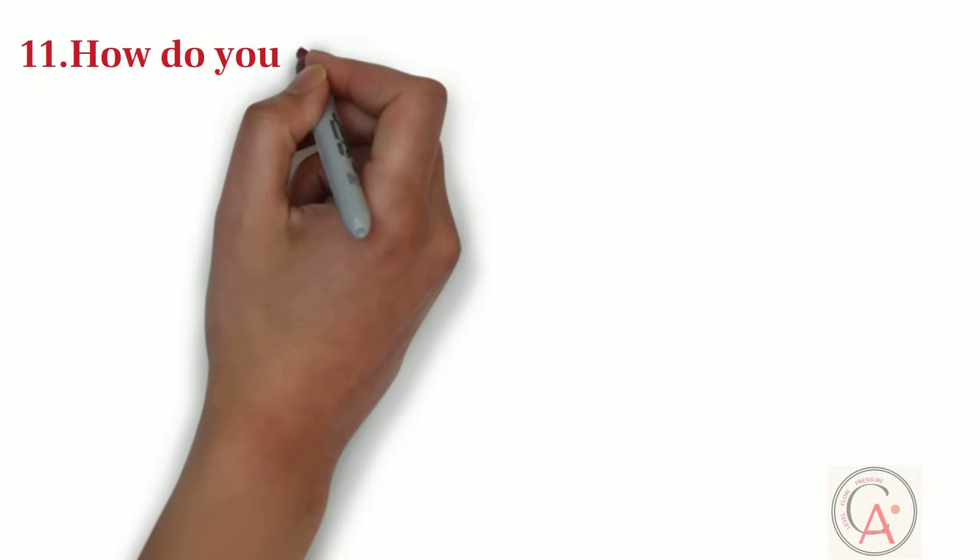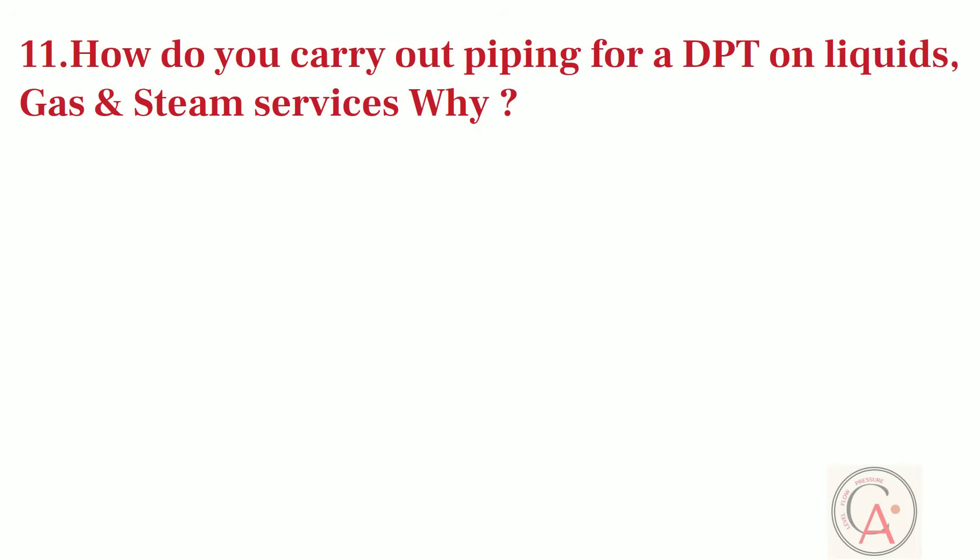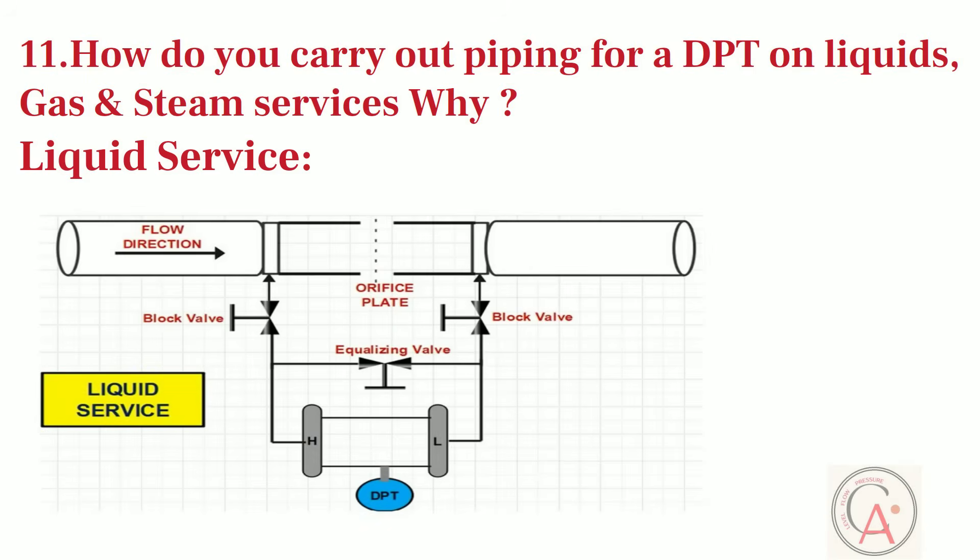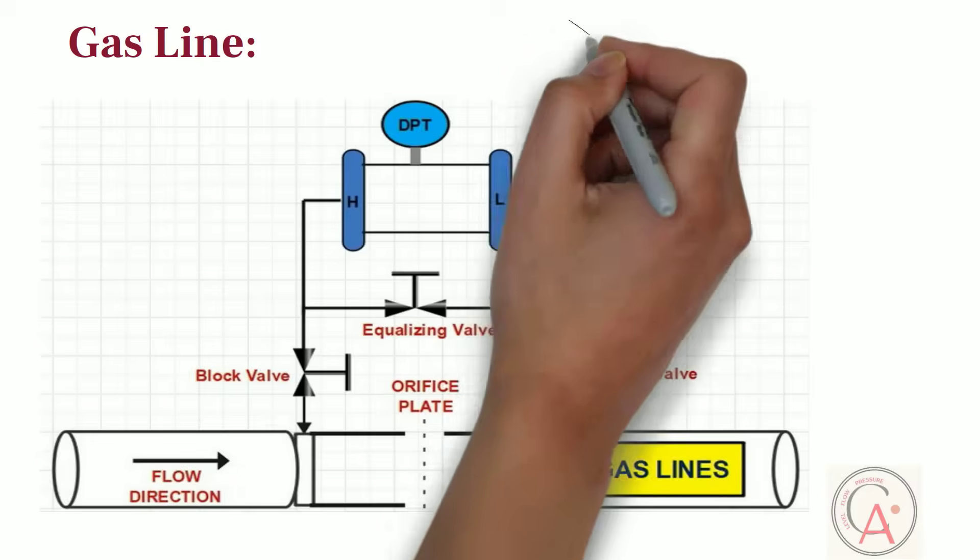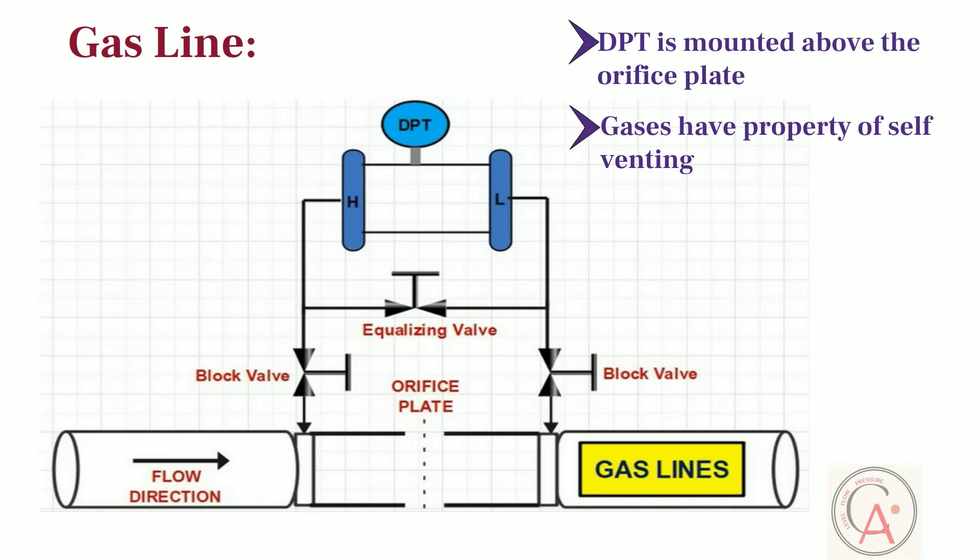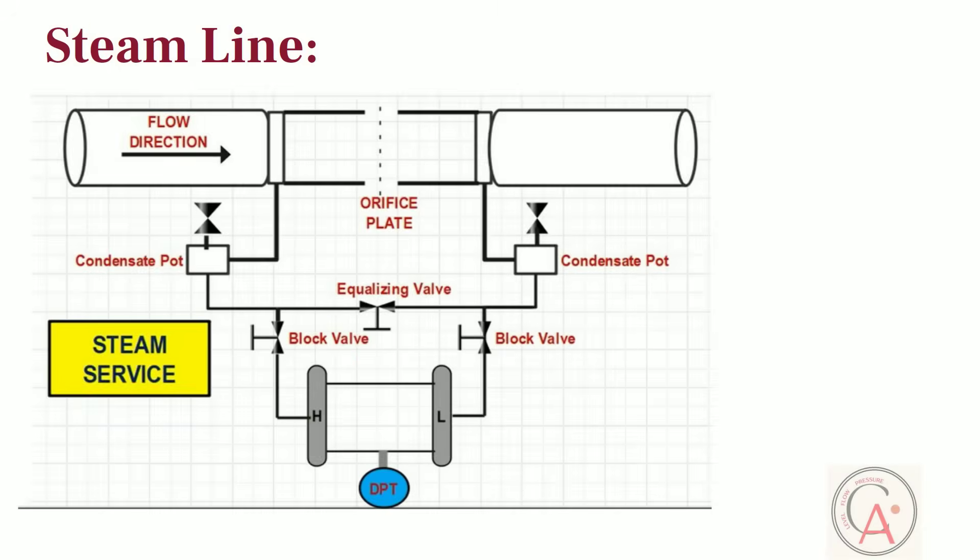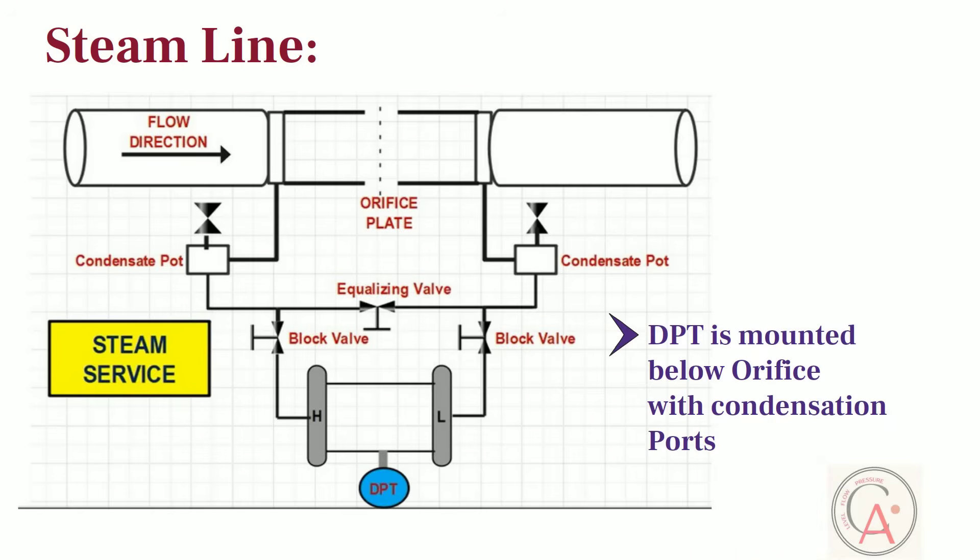Eleventh question is, how do you carry out piping for a differential pressure flow transmitter on liquids, gas and steam services, and why? As you can see from the diagram that, on the liquid lines, the transmitter is mounted below the orifice plate because of the fact that liquids have a property of self-draining. On gas service, the transmitter is mounted above the orifice plate because gases have a property of self-venting and secondly condensate formation. On the steam service, the transmitter is mounted below the orifice plate with condensate pots, and both the pots should be at the same level.